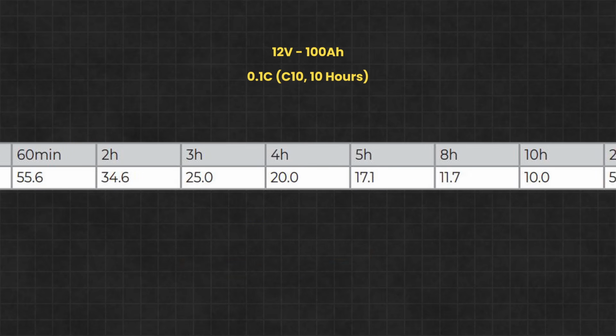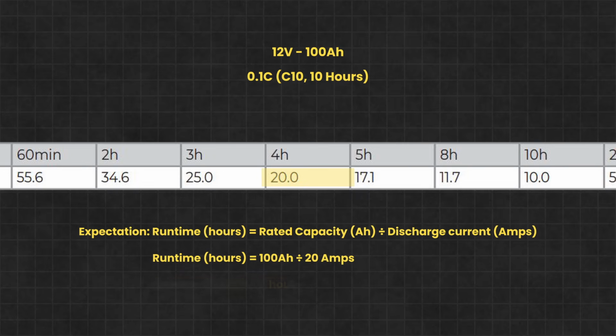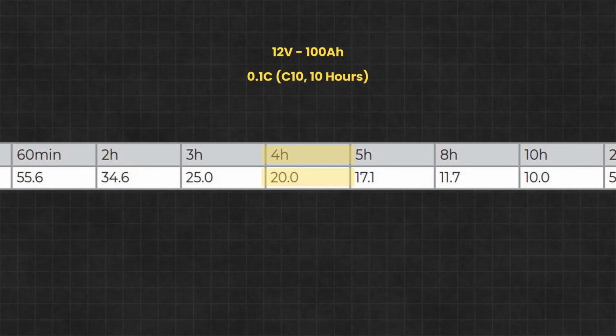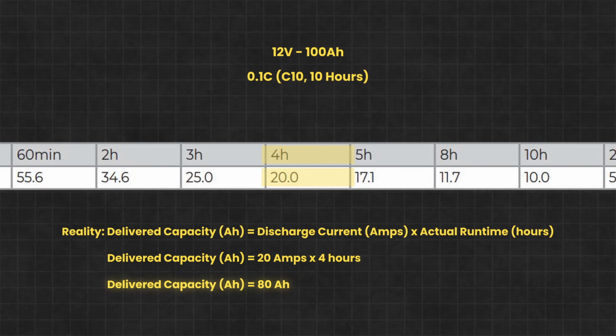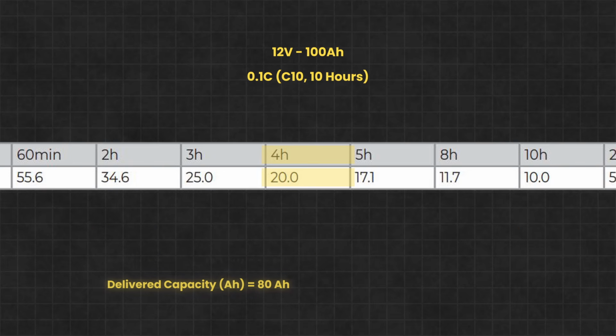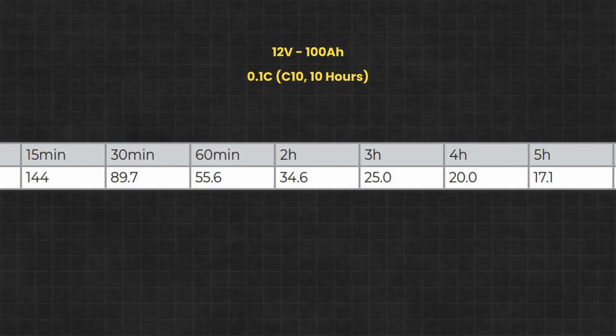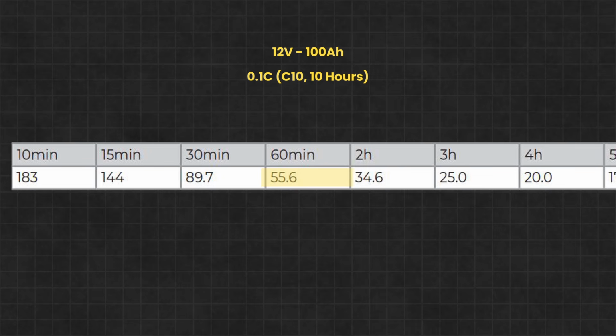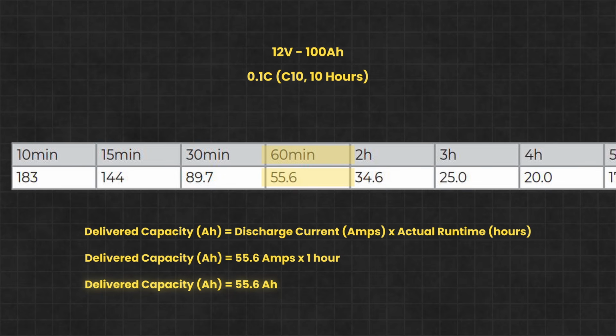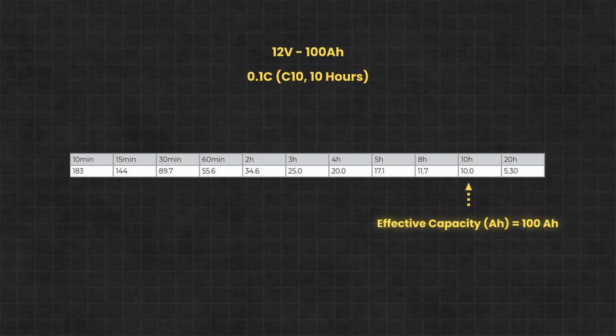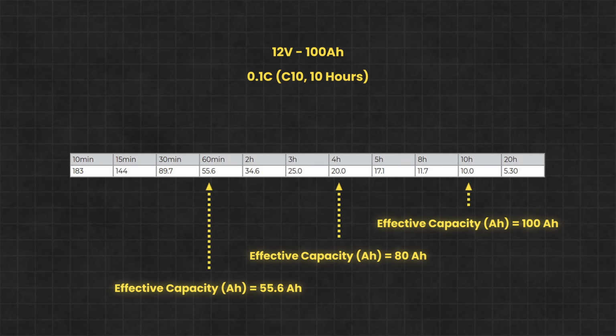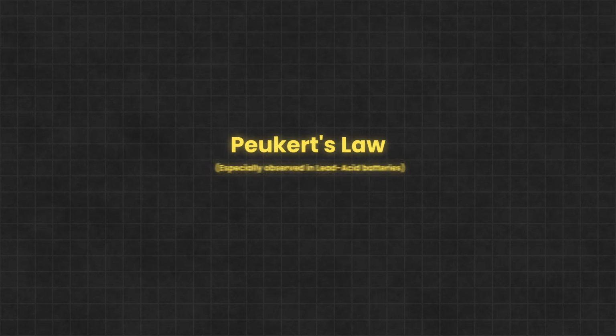But now let's double the current and discharge the battery at 20 amps. You would expect it to last for 5 hours, right? Since 100 amp hours divided by 20 amps equals 5 hours. But no, it only lasts for 4 hours. Multiply that by the discharge current and you're only getting 80 amp hours of actual usable capacity. And if we keep increasing the discharge current, the capacity drops even further. For example, according to the datasheet, if you discharge the battery at 55.6 amps continuously, it only lasts 1 hour. That gives you just 55.6 amp hours, which is almost half the rated 100 amp hours. So to recap, at 10 amps you get 100 amp hours, at 20 amps you get 80 amp hours, and at 55.6 amps you only get 55.6 amp hours. This effect is known as Peukert's law, and it mostly applies to lead-acid batteries.